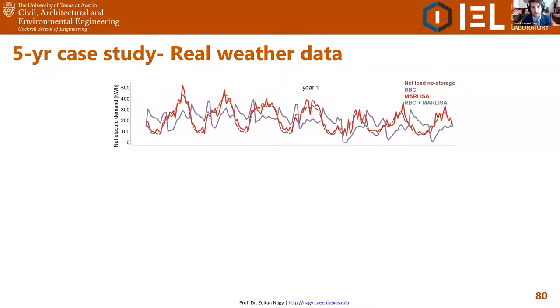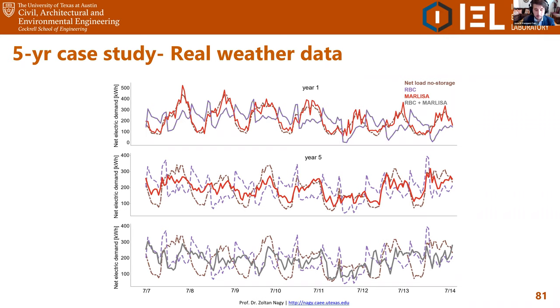Showing results for a specific summer week in year one: the RL agents are acting randomly and not particularly reducing electricity consumption peaks. But by year five, they perform much better, flattening consumption peaks and outperforming the rule-based controller. Comparing the two RL approaches in this chart, the performance metrics show that the rule-based controller pre-training combined with RL did not achieve as good a long-term result as just using the RL controller with exploratory movements from the start.